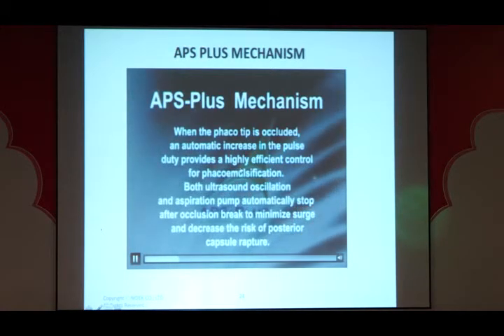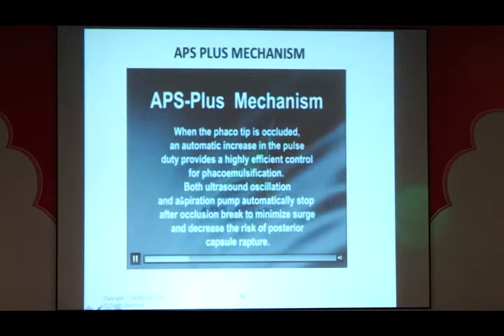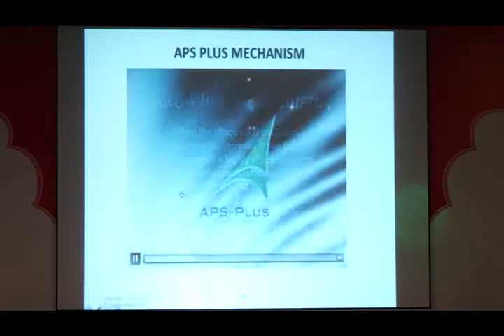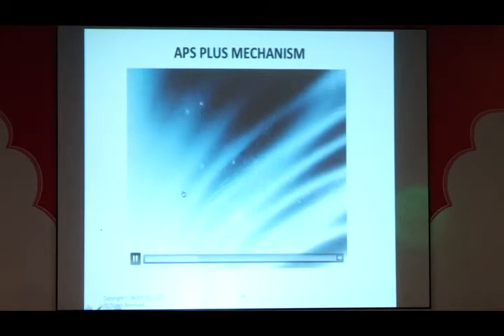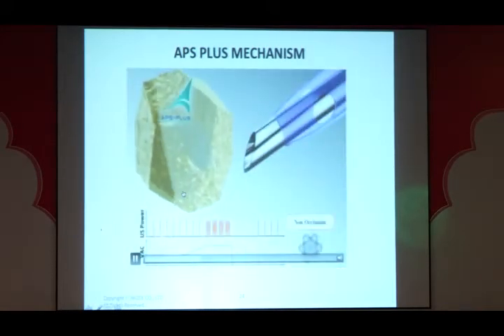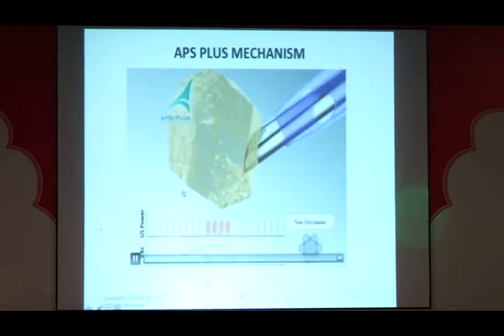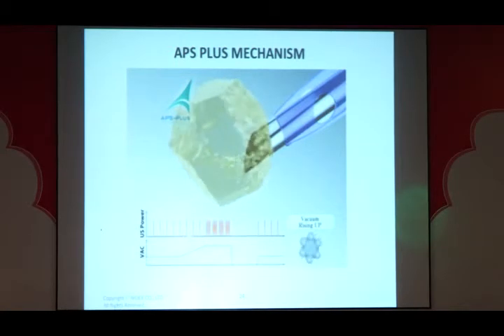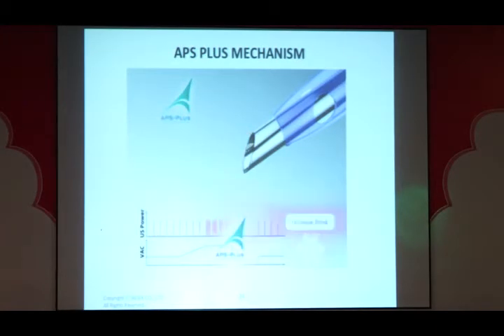So when you need more energy after occlusion, that is when it provides more energy. Also, as I said, when the occlusion breaks, immediately you have the aspiration stop and you have the phaco stopped for a time which can be programmed. So it can be about 2 seconds, and that is a great mechanism for preventing surge and preventing damage to the posterior capsule. So here you see that this mechanism is functioning.